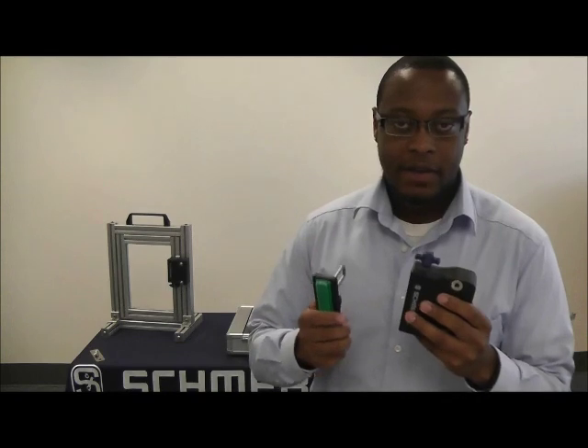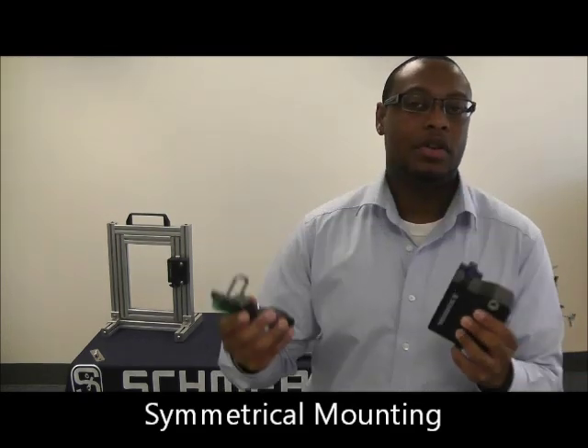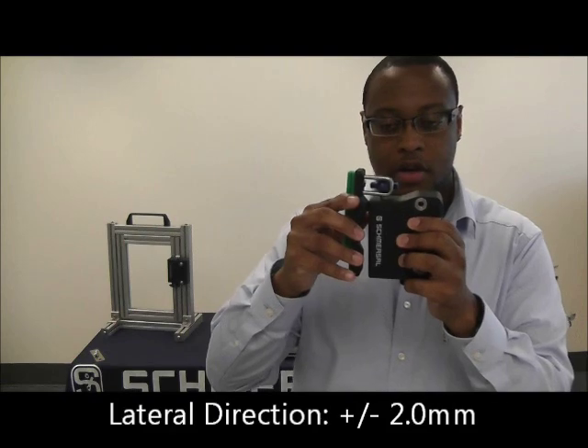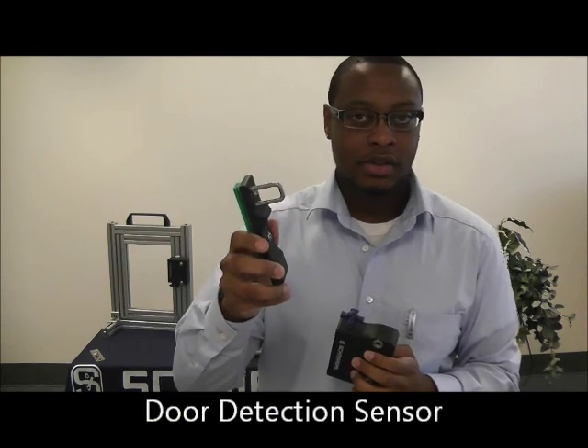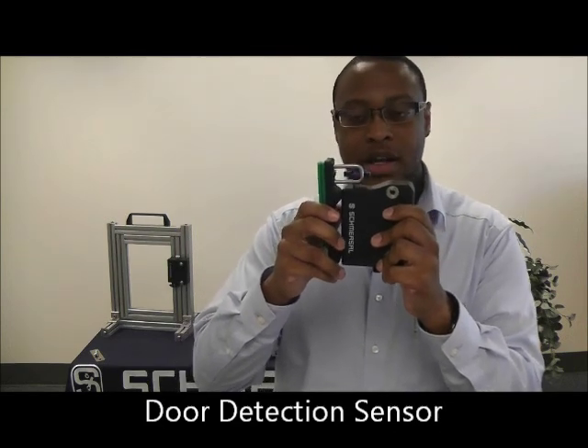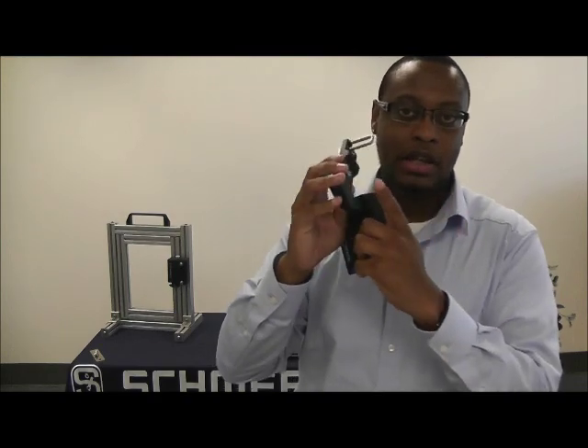When we look at the actuator of the AZM300, we see that this switch is made for symmetrical mounting, so you don't have to worry about ordering a left or right-hand version. The locking portion of the actuator in this switch has a nice wide range of actuator tolerance, and the actuator itself will feature door-detection sensors. So, the AZM300 is looking to make sure that the door is closed or that the actuator is present, and that the rotary locking mechanism has turned before you can get your safety outputs. That way, an operator cannot simply go to the door and turn the locking mechanism.